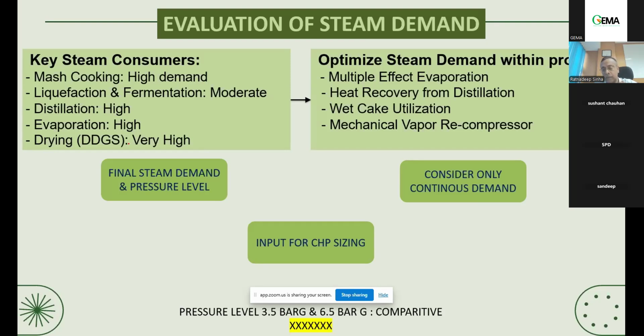So you have to calculate the normal and maximum steam demand, because finally you are demanding this steam from a steam turbine when you are going for a cogeneration plant. If you are taking from a boiler, only a process boiler, it is very easy. You take the steam demand, add a 10-15% or 20% margin, and size the boiler. But it is not so easy when you are sizing the cogeneration plant, where you are taking extraction or making a back pressure turbine for the plant. So here you have to be very careful, because you cannot over specify and you cannot under specify; you have to be at an optimum level while specifying the steam demand.